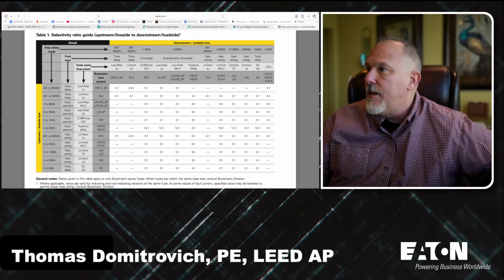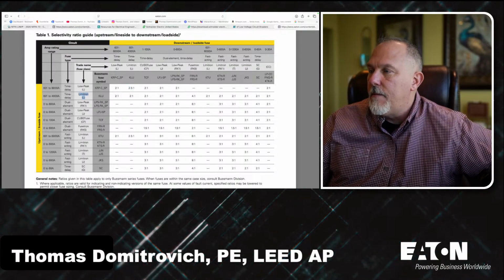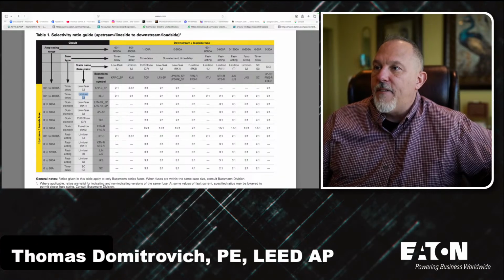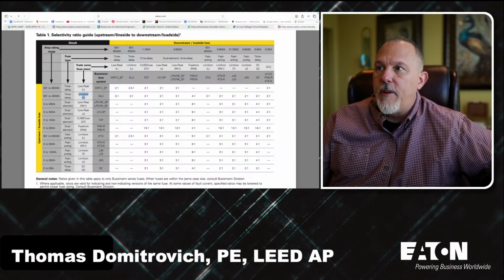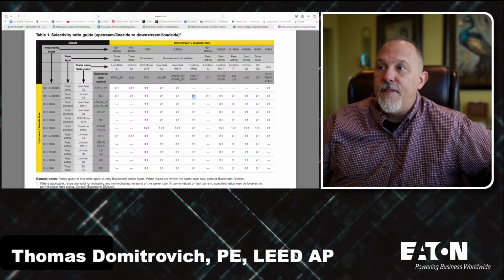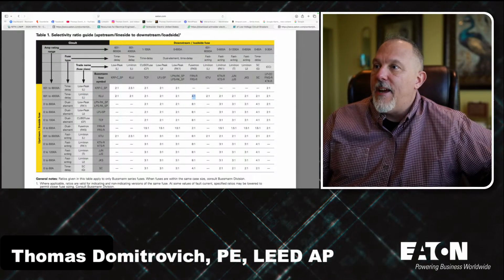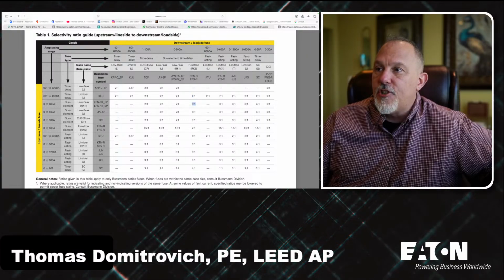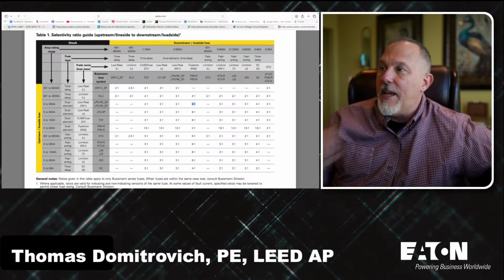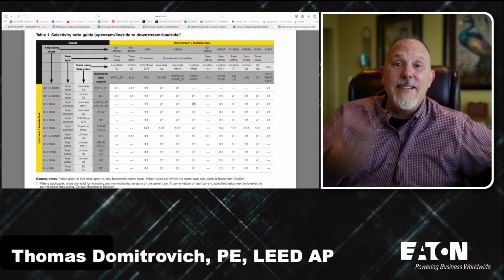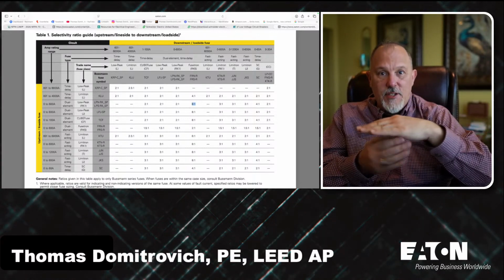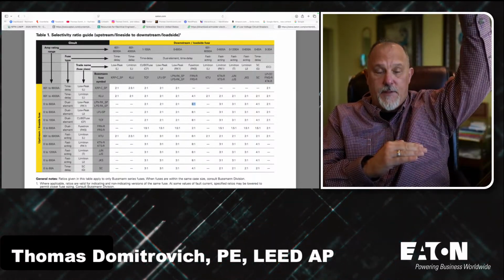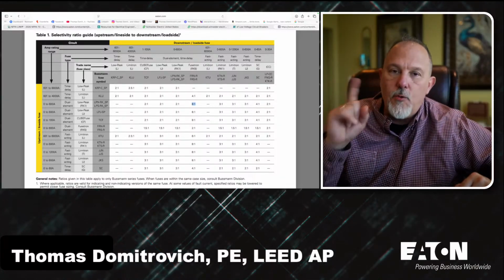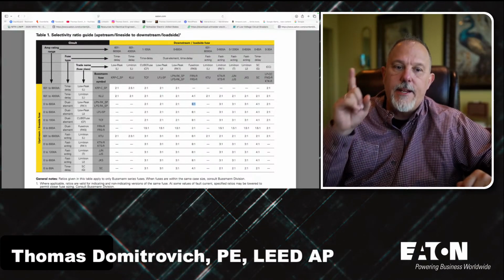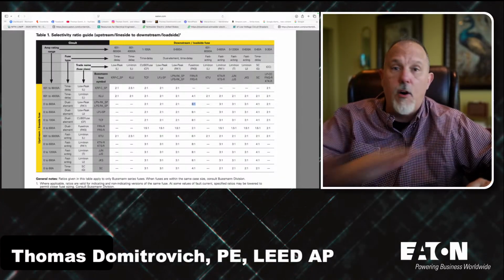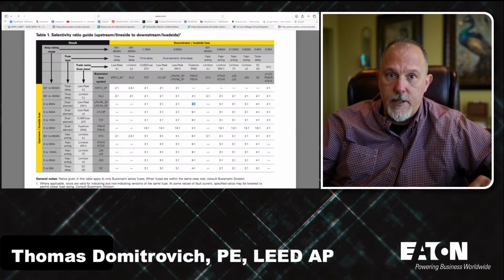Now, if you look at the Limitrons, and you have an upstream or a downstream of an FRN, I need a 4 to 1 ratio. If I have the FRN downstream of an LPNRK, I have an 8 to 1. So if I have a 100 amp fuse downstream, that means I need 800 amps of fuse upstream. So you go to the tables, and it's not a true statement to say all fuses are 2 to 1. Okay?